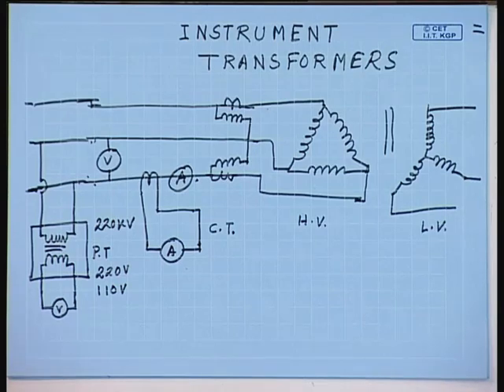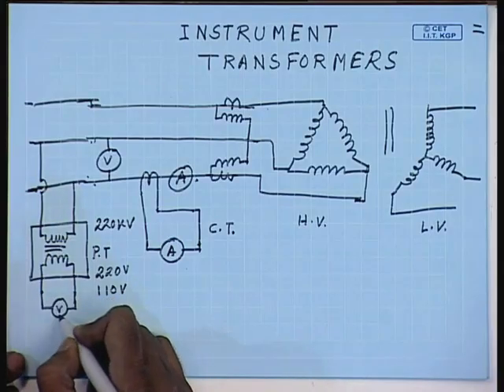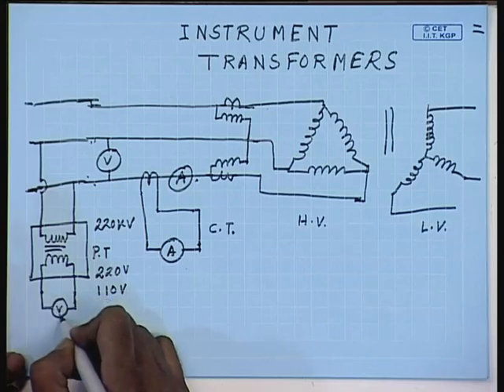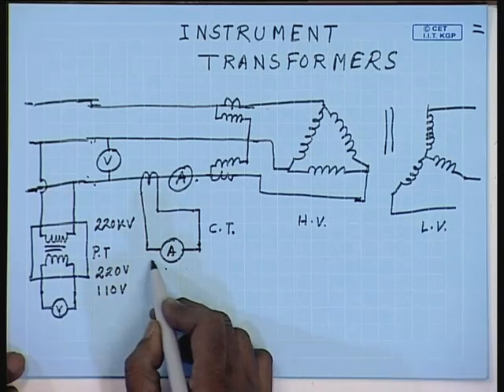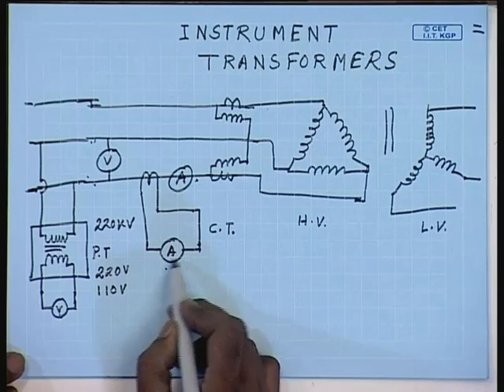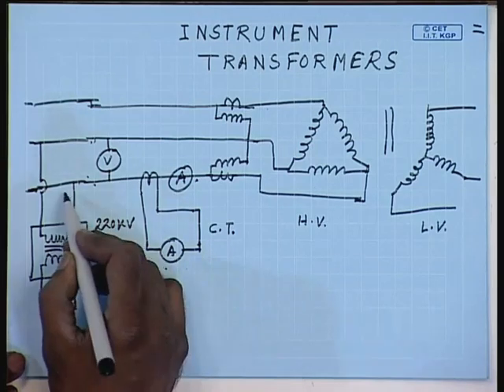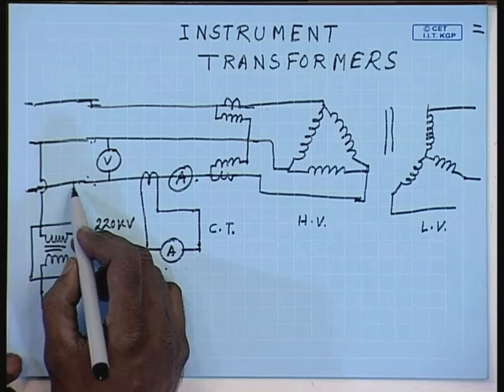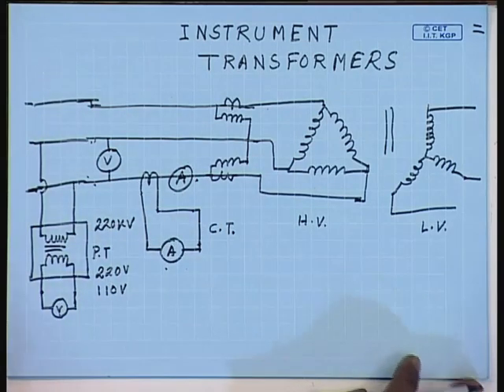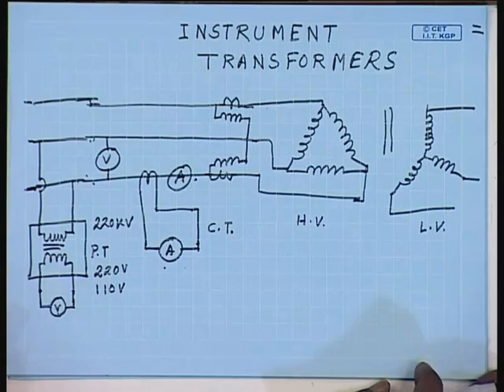Now, the working principle of these transformers is similar to normal single phase transformers. However, special care has to be taken so that the voltage appearing across the voltmeter here, or the current flowing through the ammeter here, are in proportion to and in phase with the high voltage side or high current side voltages and currents.